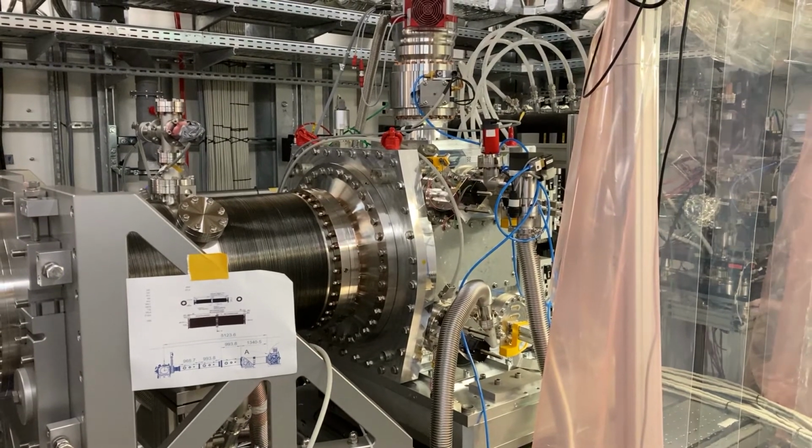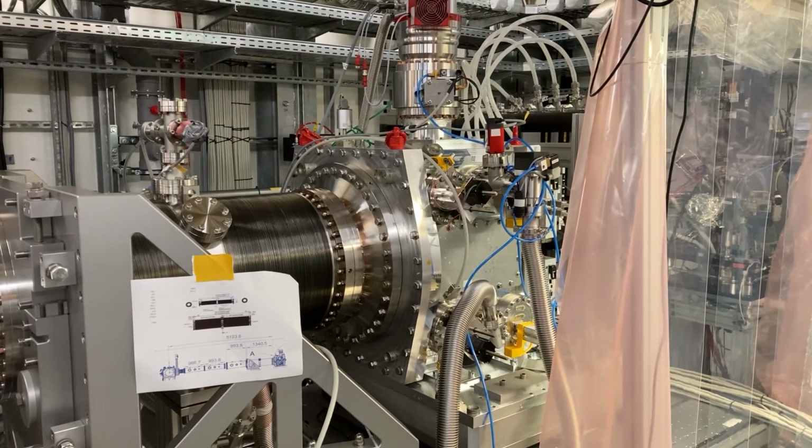This is a very special detector because it allows a very high frame rate. We can record up to 8,000 frames per second with this detector. But this is not only the last point of our instrument. Actually, this detector has a hole in the center that allows the direct beam to go through the detector. And this finally impinges on another detector that just records the transmitted intensity. And with this, for instance, we can do absorption spectroscopy and look at this at the same time as scattering.